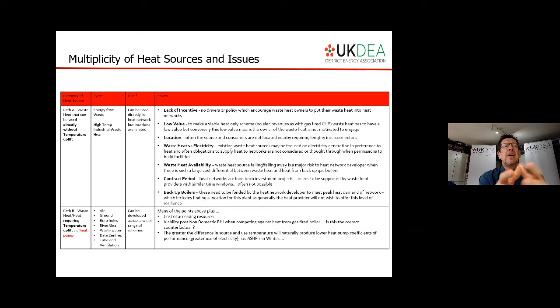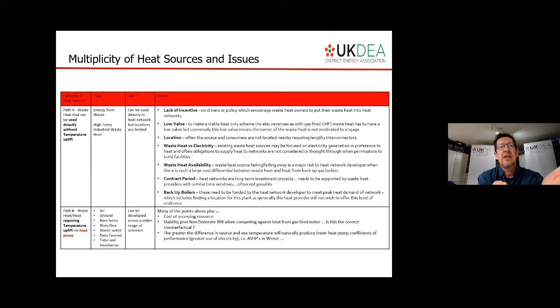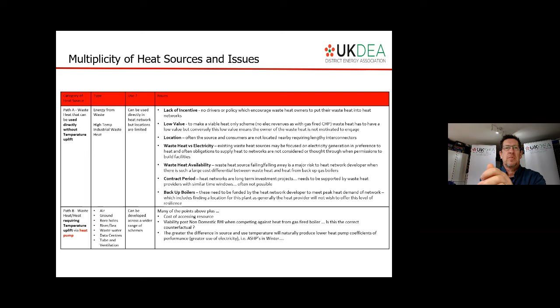A number of other issues: contract period, you've still got to put in place all the backup boilers, those have got to be located and found. And there are two different types of waste heat source. There are those at a temperature that could be used directly without a heat pump, like energy from waste or high temperature industrial waste heat. Then there's the vast majority of sources, those lower temperature sources which do need heat pumps: air, ground, boreholes, river, sea, wastewater, etc. Each of those needs an individual consideration, and each brings its own problems.